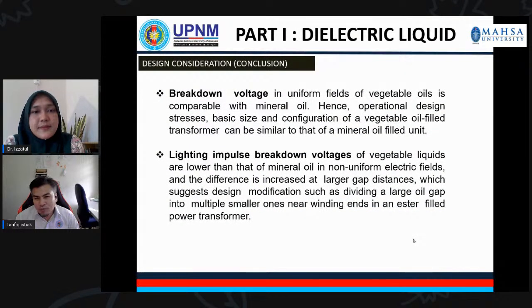So what I can conclude from the liquid insulation study is, first, the AC breakdown in the uniform field of the vegetable oil is comparable with the mineral oil. Meaning that the difference is not so much. So in terms of design, operation design stress, the basic size and configuration of a vegetable oil filled transformer can be similar to the mineral oil filled unit. Meaning that we can design a similar size of transformer to the currently used mineral oil one.